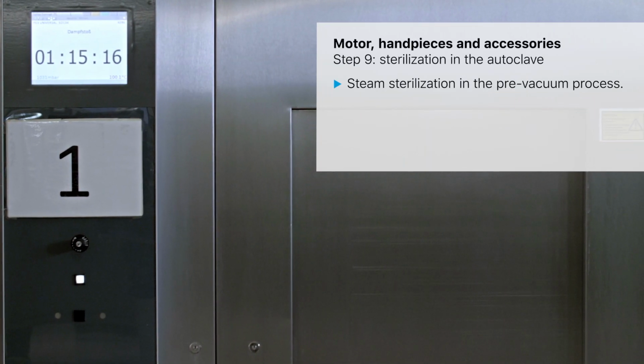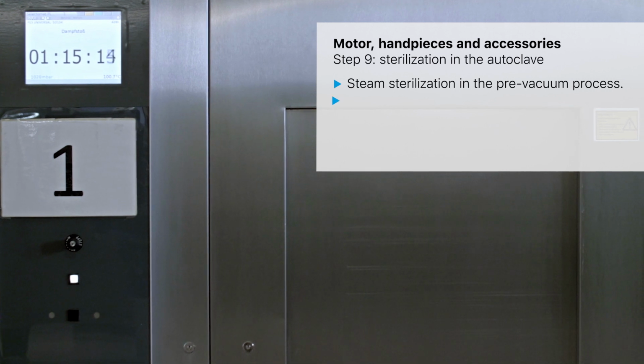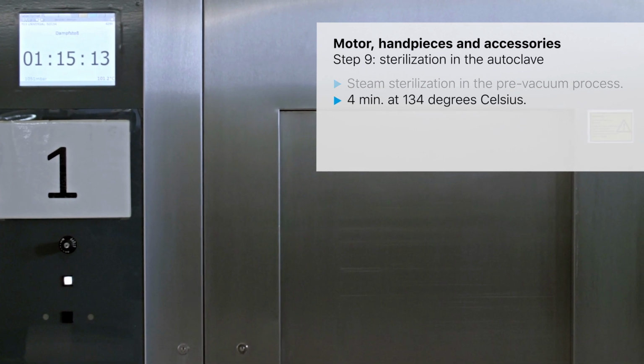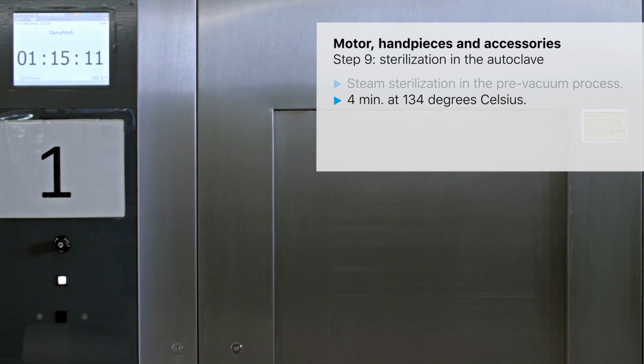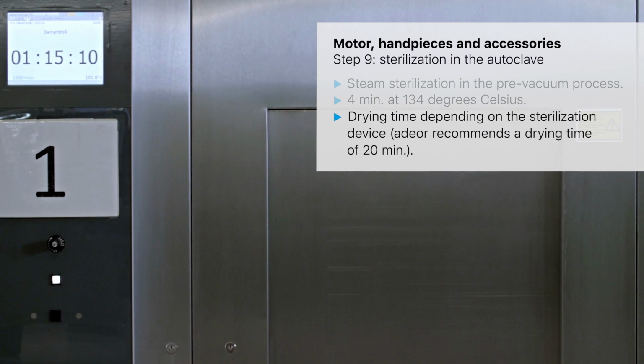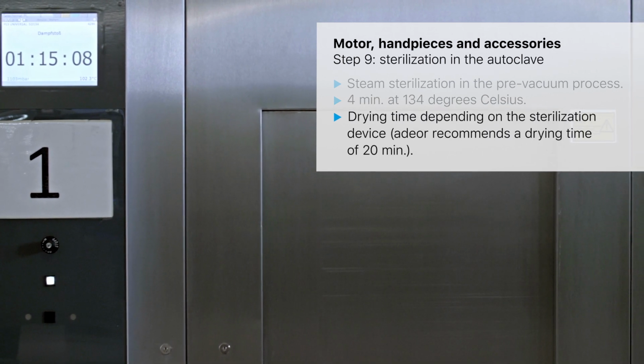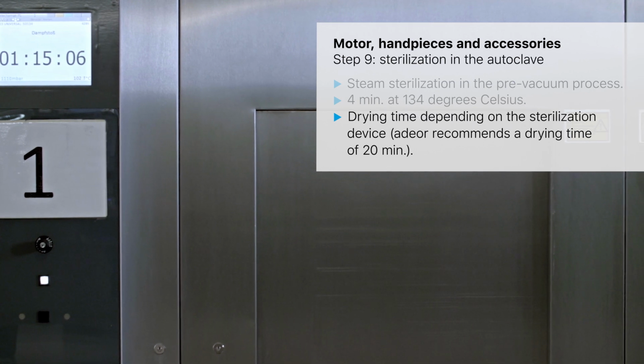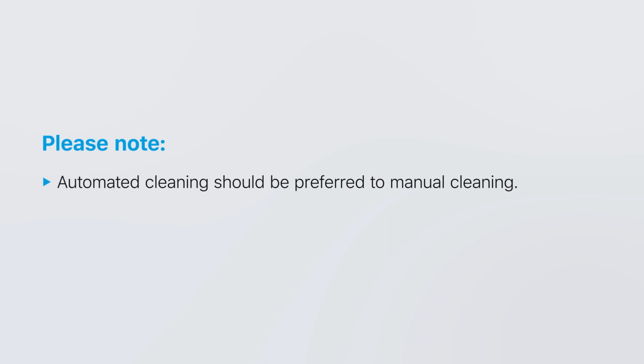Steam sterilization in the pre-vacuum process. 4 minutes at 134 degrees Celsius. Drying time depending on the sterilization device. adeor recommends a drying time of 20 minutes. Please note, automated cleaning should be preferred to manual cleaning. Never clean the system in an ultrasonic bath.